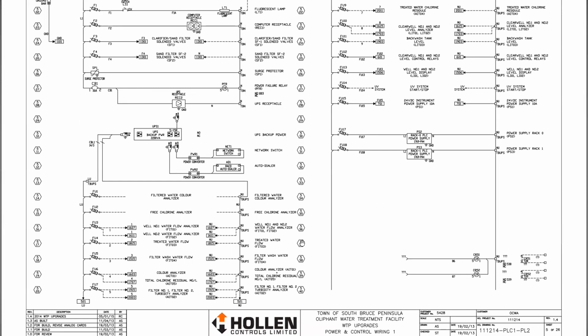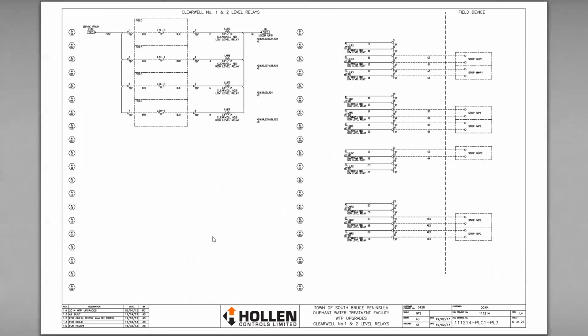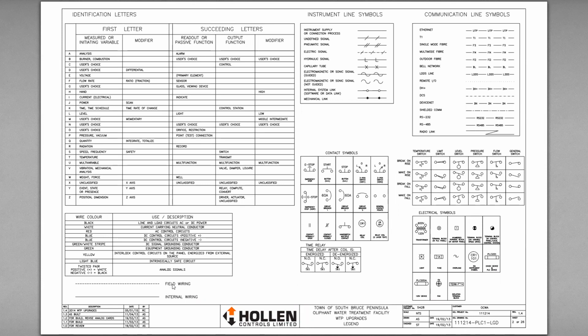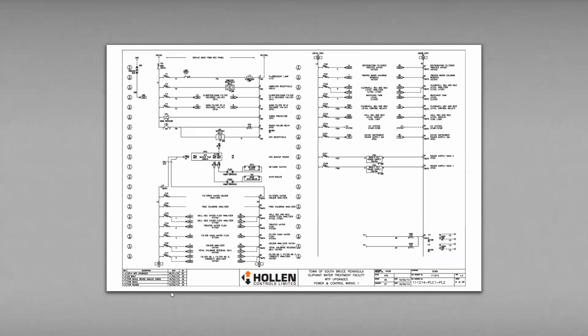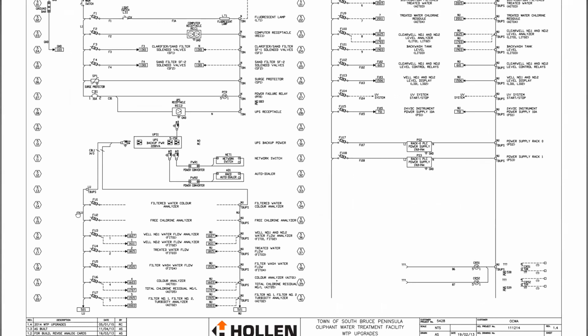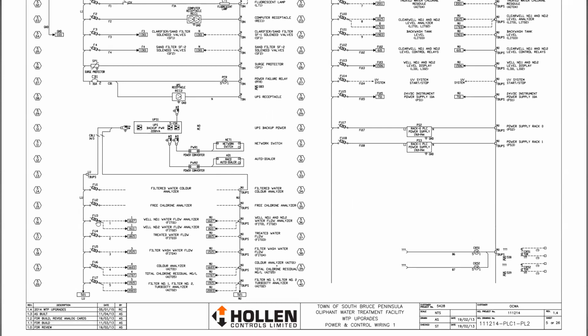This one's not showing those squiggly lines. It's giving actual blocks where these wires will leave and go to those devices. This dashed line, if we go back to this drawing set's legend, you can see that field wiring is dashed and internal wiring is solid. So I would take that to mean that all these solid lines are internal to the control panel, and anything dashed is leaving the panel, going out to these devices. So on fuse 3, we've got flow analyzers. On fuse 4, we've got a flow meter. Fuse 5, we got, excuse me, filter wash flow meter.